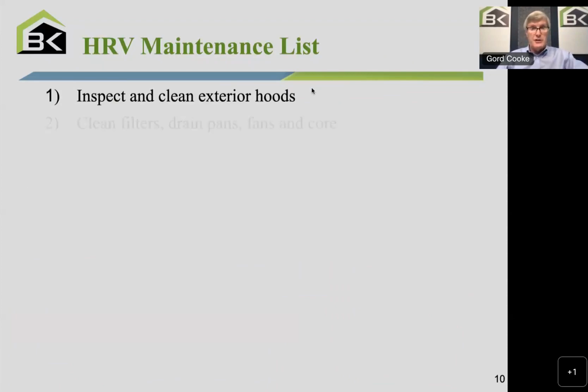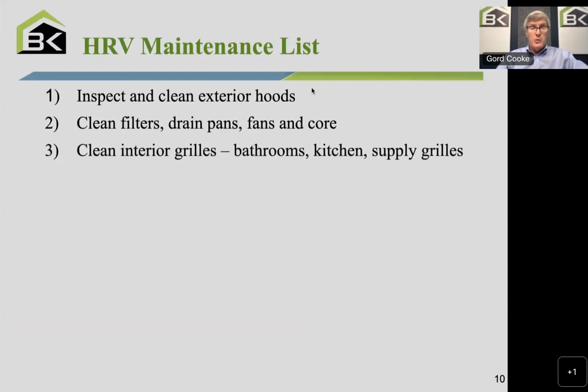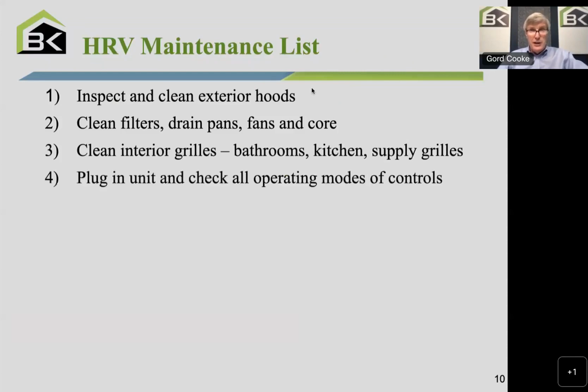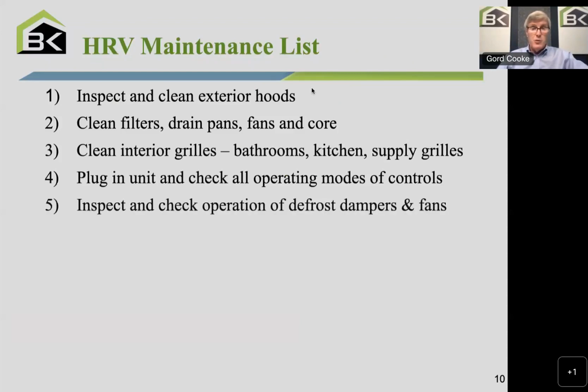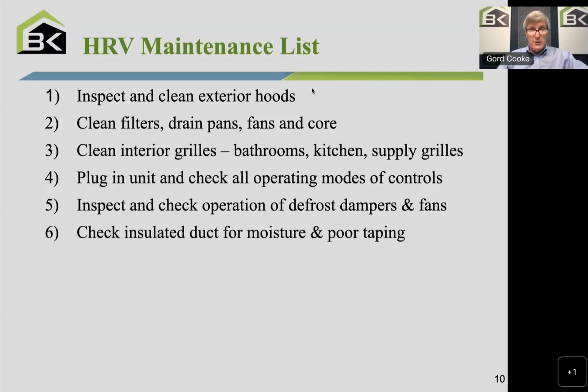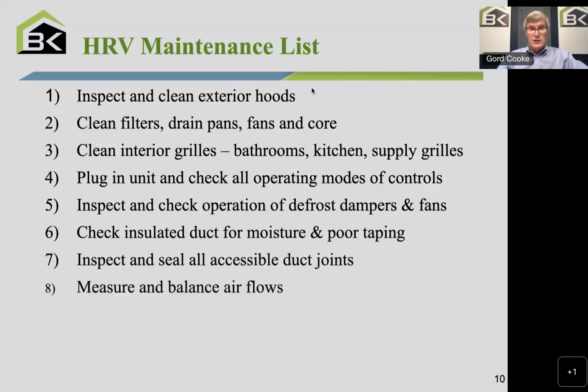We're going to inspect and clean exterior hoods. We're going to clean filters, drain pans, fans, and cores inside the unit. We're going to clean interior grills in the bathroom, the kitchen, and even the supply grills in the bedrooms. We're going to think about plugging the unit in after we've done the cleaning and checking all the operating modes to make sure they're all working correctly. We're going to inspect and check operation of the motors and the fans within the unit. We're going to do a quick check of the ductwork itself to make sure it's properly installed and not causing issues. And that includes inspecting and sealing off any accessible duct joints.